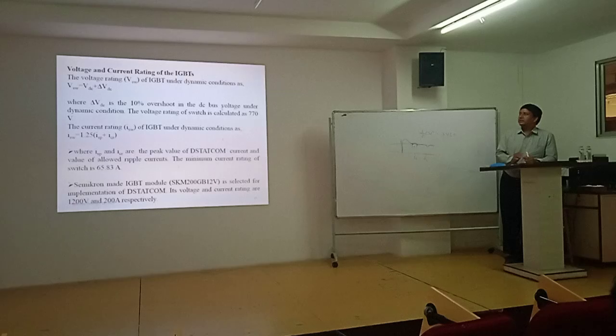How can we select the voltage and current rating of the IGBTs? The switch rating you can take as DC bus voltage plus 10% change. Our DC bus voltage is 700, plus 10% change, so you get around 770. But a 770 volt IGBT you will not get, so you can take 1000 or 1200 depending on the condition. If we are going to manufacture, then you can take a value near this.